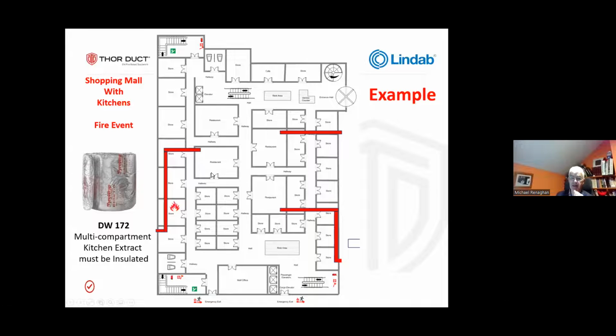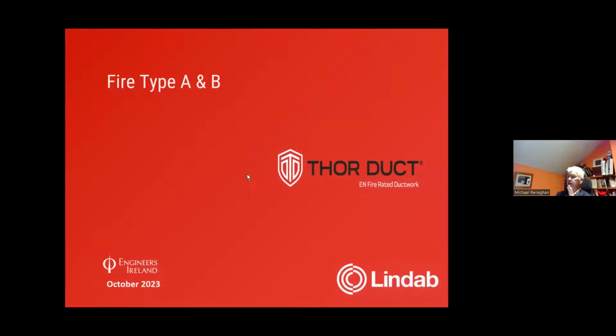The ASFP released a document about 6 months ago where they are recommending inside the kitchen that the insulation performance should be a minimum of 30 minutes. So even inside the kitchen, they're thinking you need to have some sort of protection against that grease igniting to aid escape. So that is something that has recently been issued. And again, it's not mandatory, it is guidance, but it's something worth considering. So that's the risk with the kitchen and the risk with the smoke.